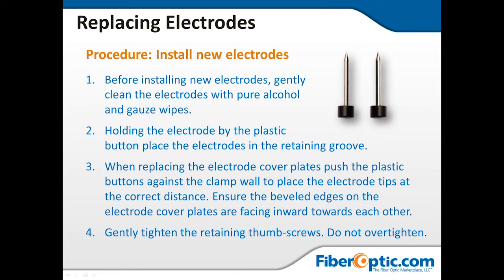Installing new electrodes. Before installing new electrodes, gently clean the electrode with a pure alcohol and gauze wipe. Holding the electrode by the plastic button, place the electrode in the retaining groove. When replacing the electrode cover plates, push the plastic button against the clamp wall to place the electrode tips at the correct distance. Ensure the beveled edges on the electrode cover plates are facing inward toward each other. Gently tighten the retaining thumb screws.